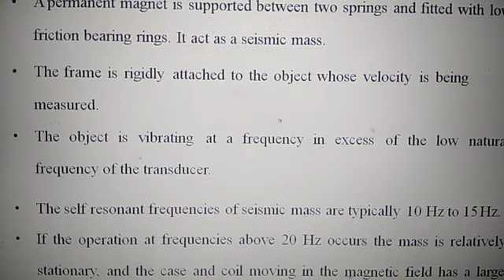The object is vibrating at a frequency in excess of the low natural frequency of the transducer. The self-resonant frequencies of the seismic mass are typically 10 Hz to 15 Hz. It's a low frequency. If the operation is at frequencies above 20 Hz, the mass is relatively stationary, and the case and coil moving in the magnetic field have a large voltage induced in them, which is proportional to the velocity.